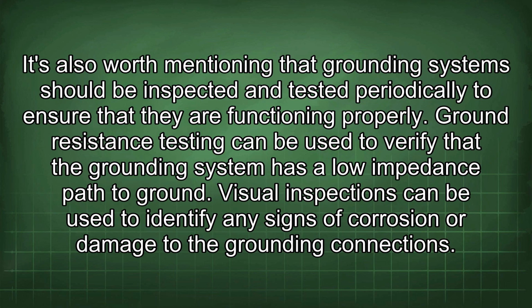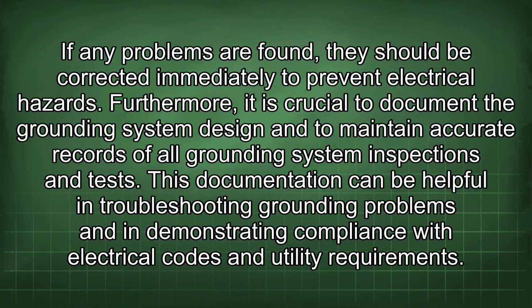It's also worth mentioning that grounding systems should be inspected and tested periodically to ensure that they are functioning properly. Ground resistance testing can be used to verify that the grounding system has a low impedance path to ground. Visual inspections can be used to identify any signs of corrosion or damage to the grounding connections. If any problems are found, they should be corrected immediately to prevent electrical hazards.